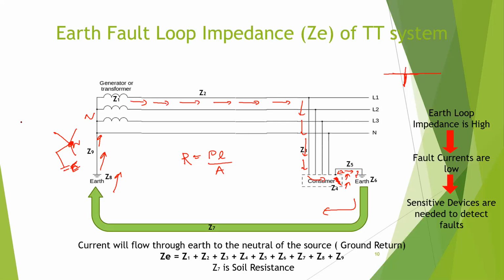Okay, so I think I am not understanding your question. Maybe you are confused with the resistivity in here? So I'm going to explain that. Okay, listen to this part. So you have an earth rod driven into your soil, and so this is the total earth, right? You have a lot of area. So this A is very high, so your resistance will get lower depending on the area, and this rho coefficient is usually higher for soil, and with higher rho and higher A, you will have some impedance through earth, but it is not as low as a metallic connection. So this is what you should understand.